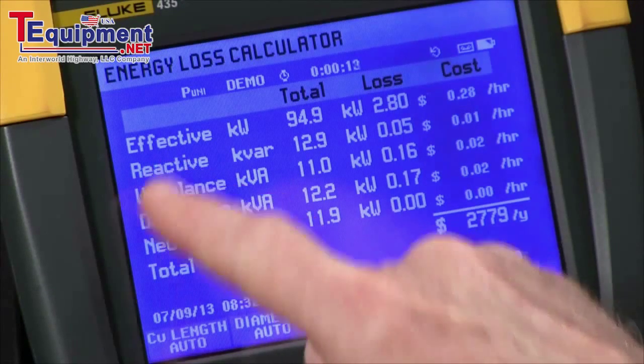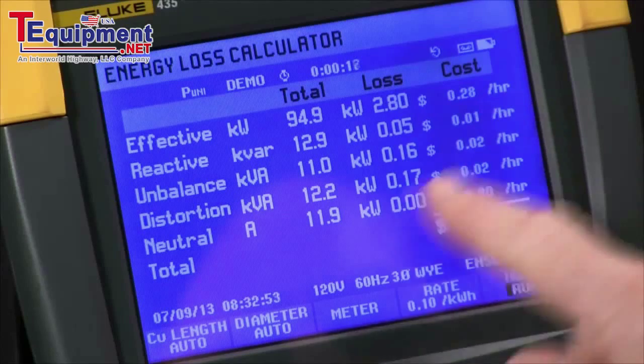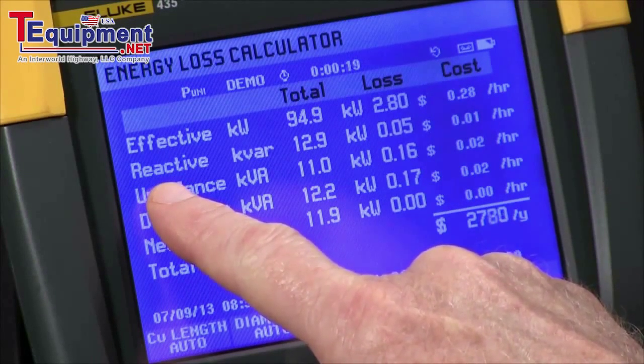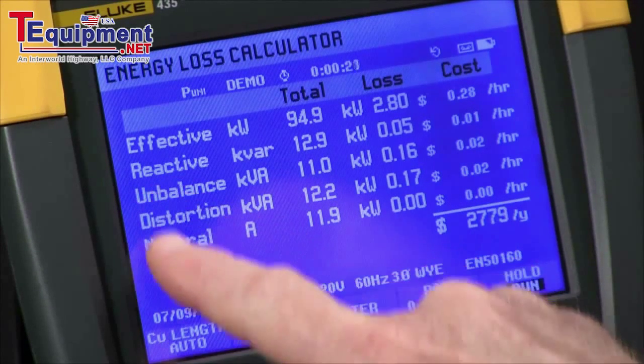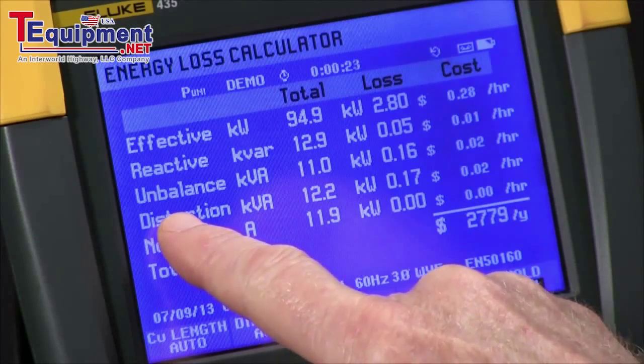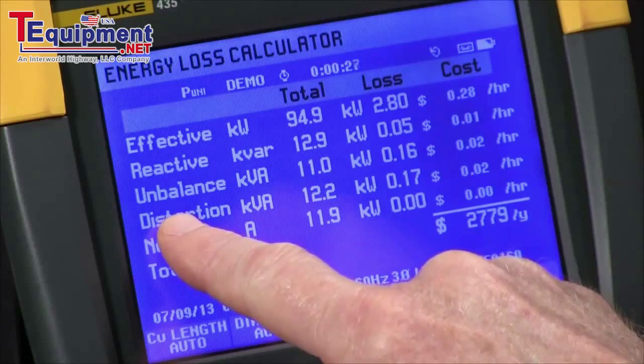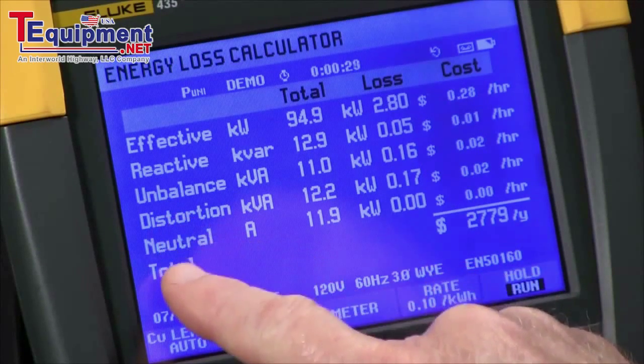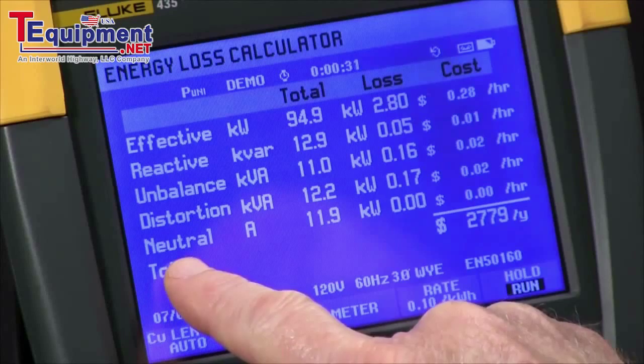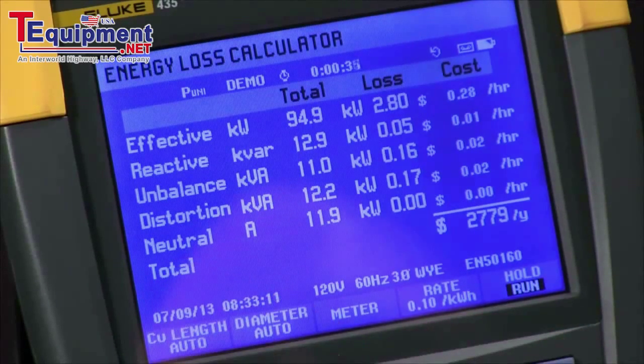Your effective power — you'll have losses due to wire resistance, and you'll see a cost per hour. Reactive power might be caused by motors and capacitors in your system. Unbalance is system unbalance in terms of not properly balanced between all three phases. Distortion would be harmonics, and the neutral losses or current flow in the neutral.